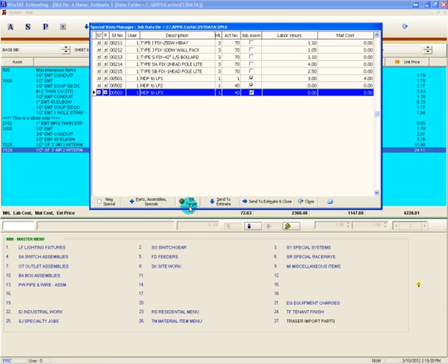The Fill Target button is used to select a different item in the job assembly to act as the target of any fill items. When adding items to a job assembly, the program attempts to anticipate a user's needs by selecting the size and quantity based on the fill target. So if, for example, a fill group contains 2 and 3 inch conduit and 2 inch was selected first, the program will always assume the item being filled is 2 inches in size.